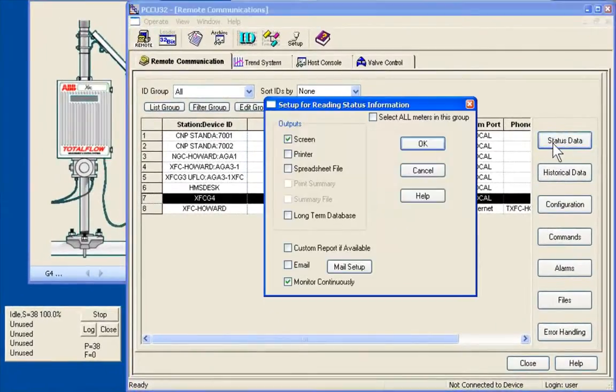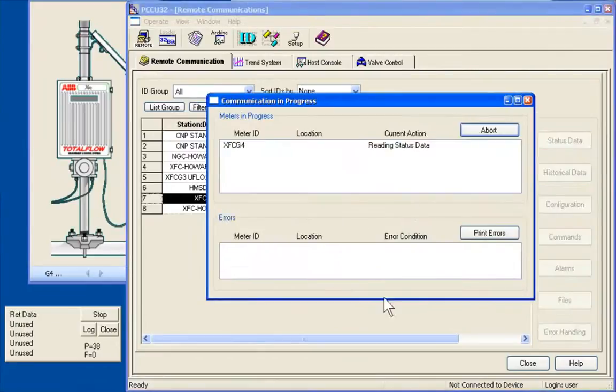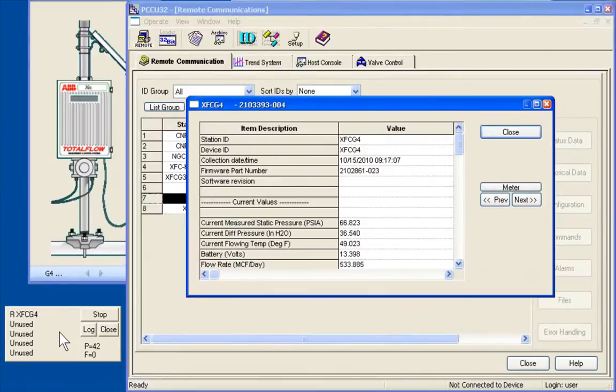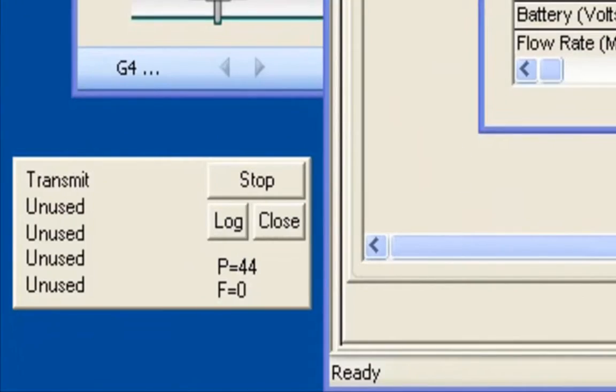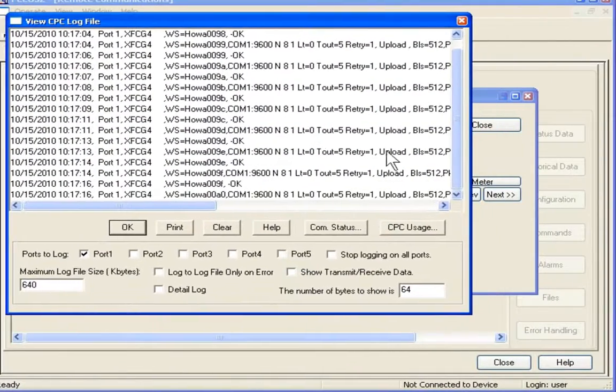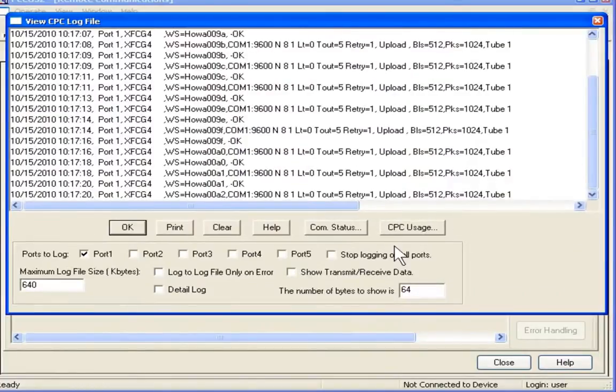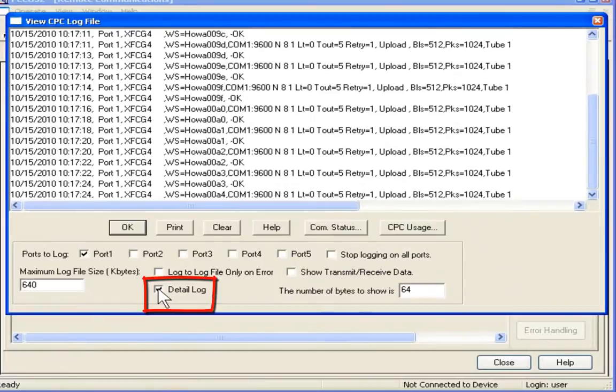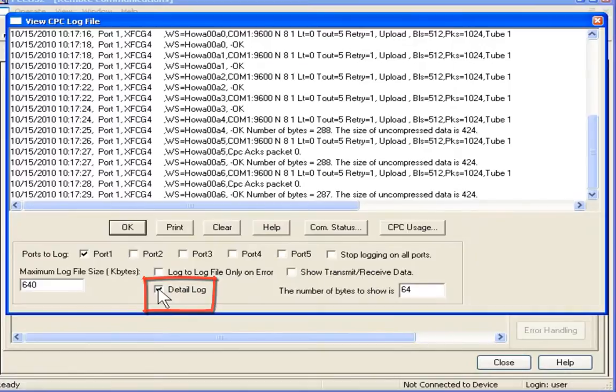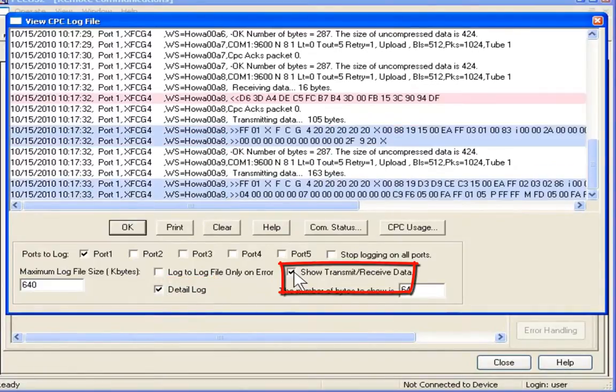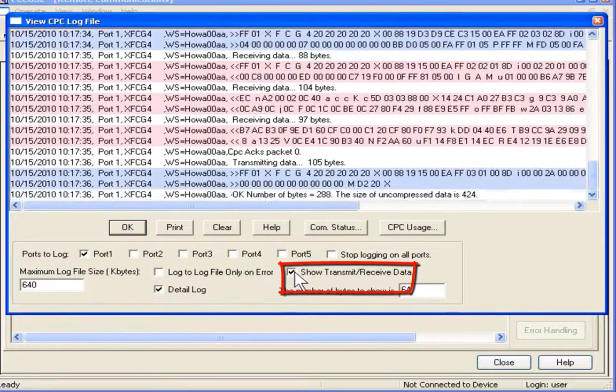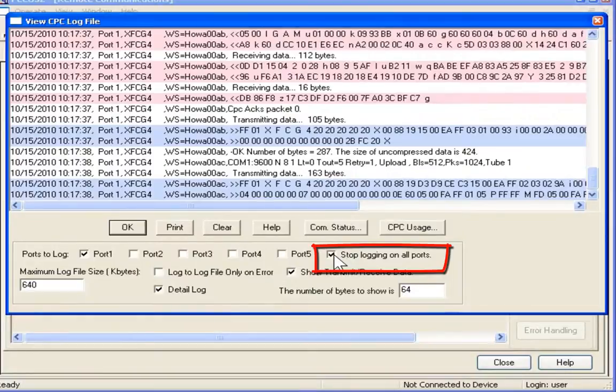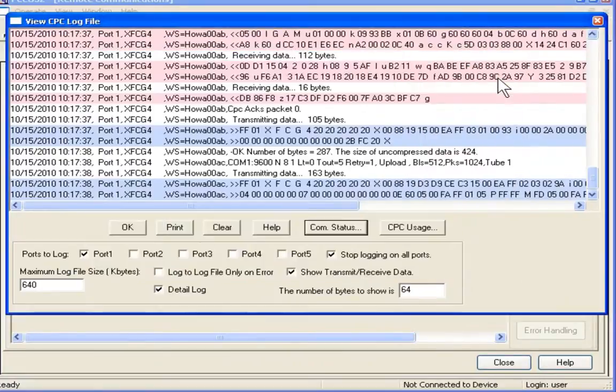We also can use the PCCU log to actually help us with determining what our status of communication is. So first, I can establish communication with the G4. Then we'll go to the CPC and look at the indication there. And I'll press log. And we'll get the screen you see here. As you can see, we're getting statuses come across. We can also select detail log, which we get more detail about the communication. And we can further actually select transmit and receive data to get more data. We can stop the log, if we wish.